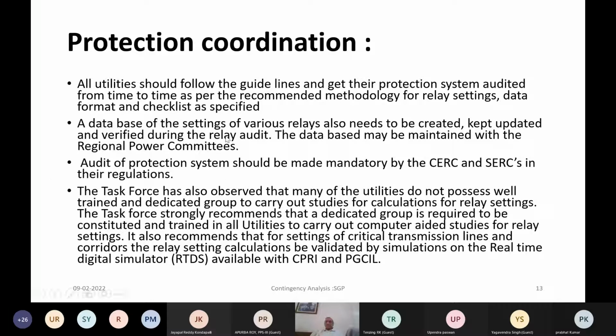So a database of the settings of various relays also needs to be created, kept updated and verified during the relay audit. The database may be maintained with the regional power committees. One observation after the 2012 grid collapse is that there were a number of location discrepancies between the actually adopted settings compared to the recommended settings by the planning group, or whoever is responsible for protection planning. So this audit will reveal such deviations.